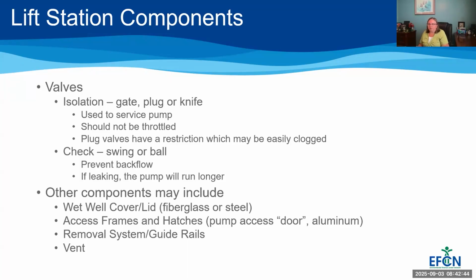And then other components: your wet well cover, your lid, those can be fiberglass or steel. Access frames and hatches, these are your kind of access doors. They're typically aluminum. Your removal system to pull your pumps, the guide rails, and the vent that allows the gases to escape from the lift station.